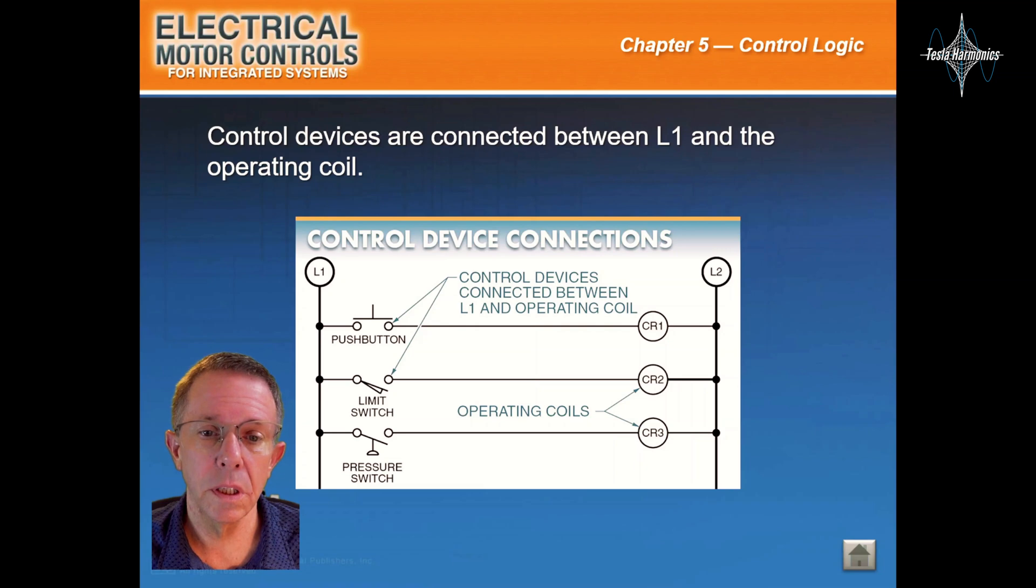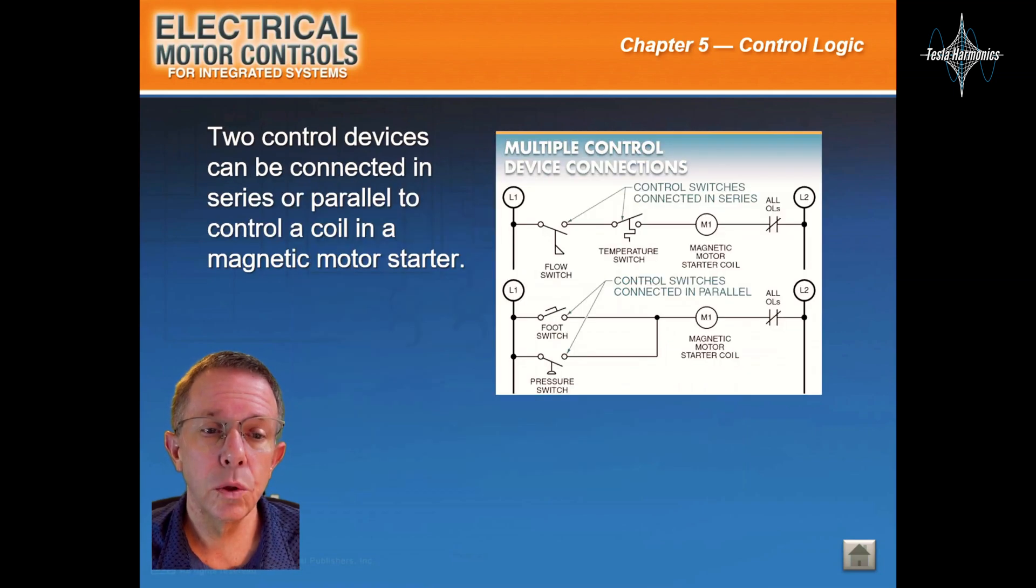Control devices are connected between line 1 and the operating coil. Two control devices can be connected in series or parallel to control a coil in a magnetic motor starter.